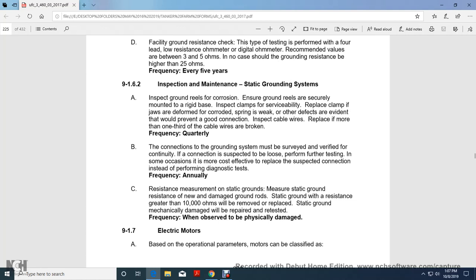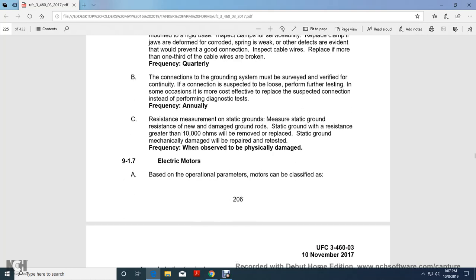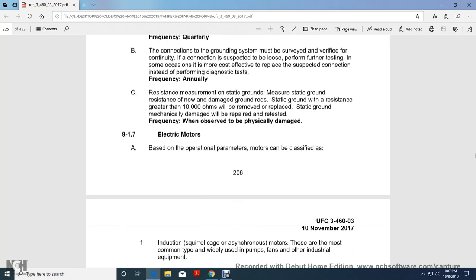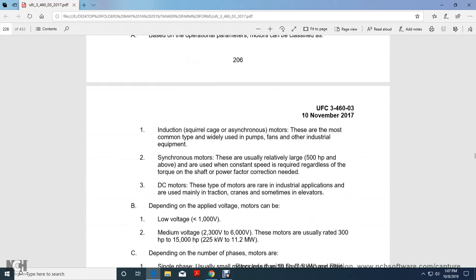Resistance measures on static ground. Measure static ground with the resistance of the new and damaged ground rods. Static ground rods with resistance greater than 10,000 ohms will be removed or replaced. Static grounds will be mechanically repaired or retested when observed physically damaged.